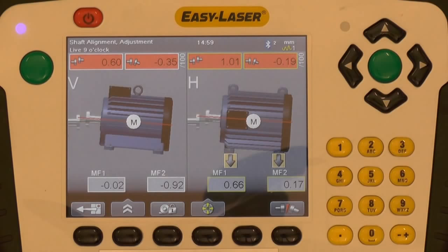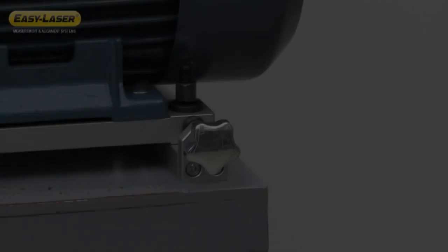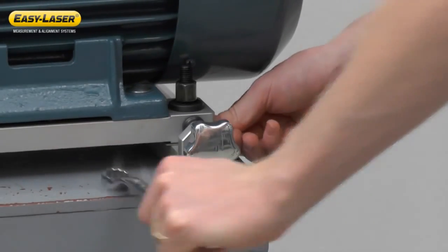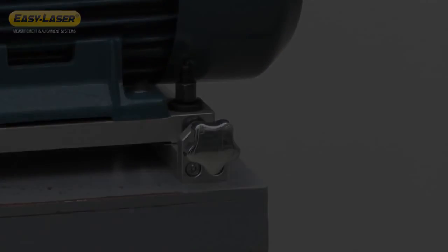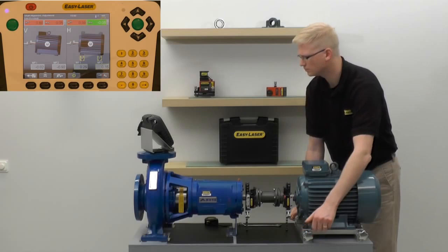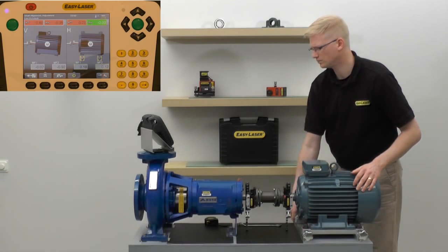The E710 calls for 0.92 mm of shims added to the back feet pair. I'm going to raise the back end of the motor by adding 1 mm shims. Once the vertical position has been corrected, I will correct the horizontal misalignment.